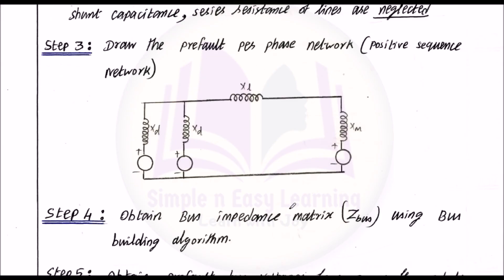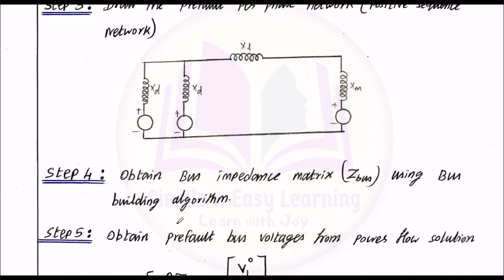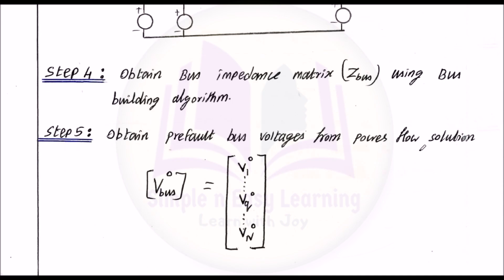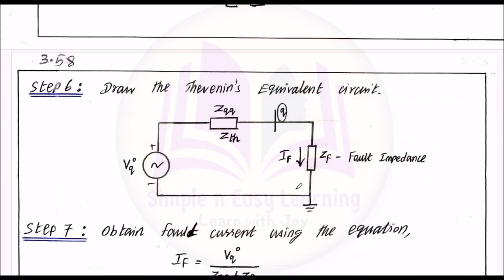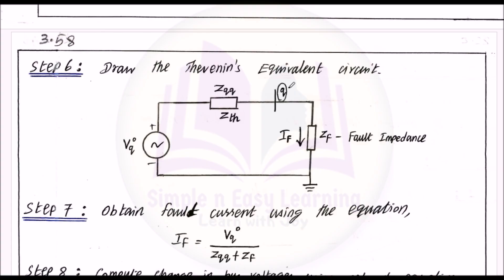Step 3 — draw the pre-fault per-phase network, the positive sequence network, which consists of two generators and one motor connected by a transmission line. Step 4 — obtain the bus impedance matrix using the bus building algorithm. Step 5 — obtain pre-fault bus voltages from the power flow solution: Vbus = [V10, V20, ..., Vn0]. Step 6 — draw the Thevenin equivalent circuit with voltage source Vq0, Thevenin impedance Zth (also called Zqq), and fault impedance Zf.